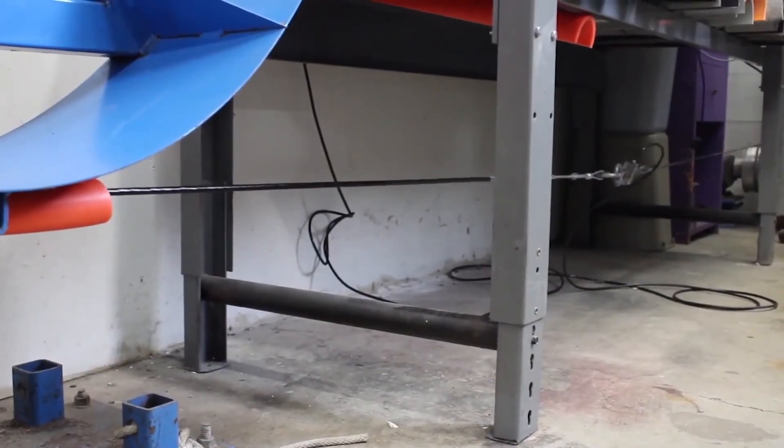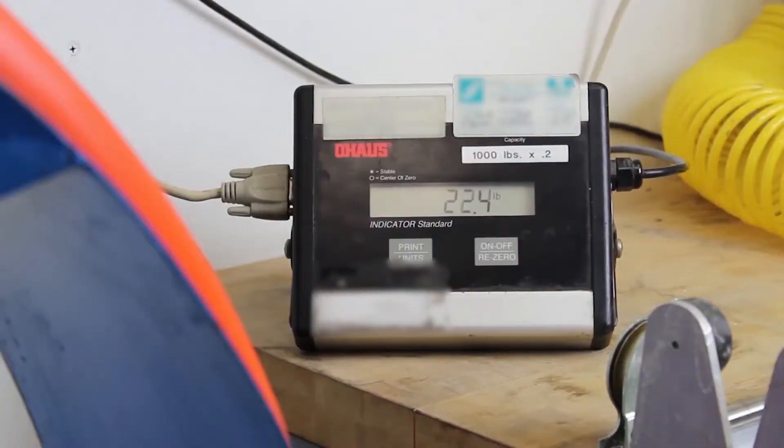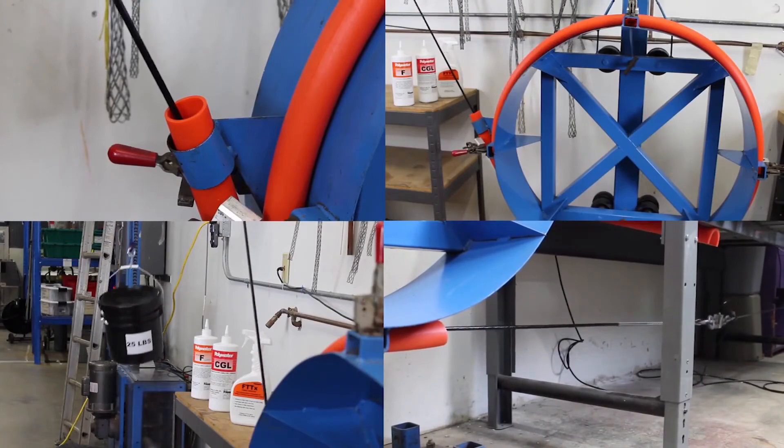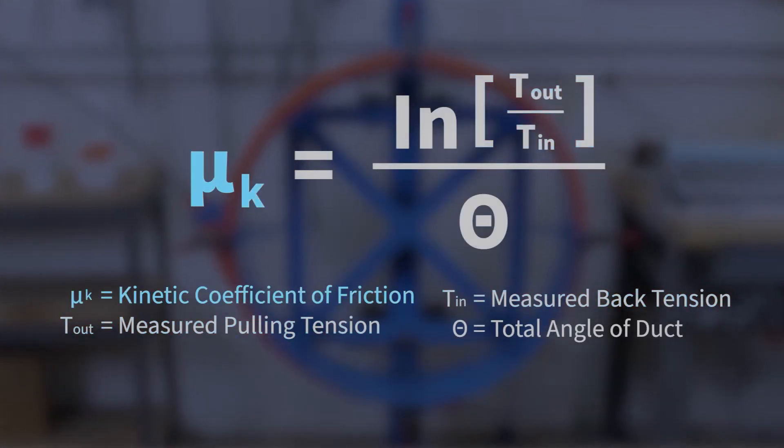A fixed back tension is attached to a pulley. The cable is connected to a load cell and pulled out at a set speed. Dynamic tension values are recorded as the cable moves through the conduit. Pulling tension is used to calculate the friction coefficient using a standard formula.